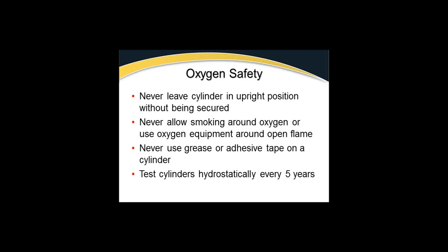And then test your cylinders hydrostatically every 5 years. Cylinders, or tanks, need to be sent away, and they'll be run through a testing process where they are submerged in water, and they'll add X amount of pressure to it and watch to make sure that the tank is holding pressure and is structurally sound.